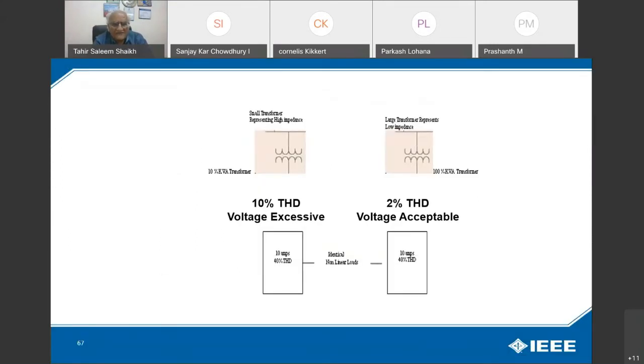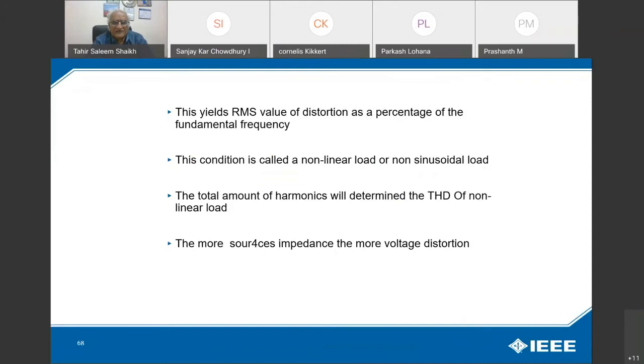Now, one solution for this is to increase the size of your power equipment. In this case, there is a transformer which gives you 10% THD voltage, and if you increase the size, it will reduce to 2%. Generally, it is good practice that you should not put a non-linear load of more than 20% on a transformer or generator. This yields the RMS value of distortion as a percentage of the fundamental frequency. This condition is called a non-linear load, a non-sinusoidal load. The total amount of harmonics will determine the THD of the non-linear load. The more the source impedance, the more the voltage distortion.